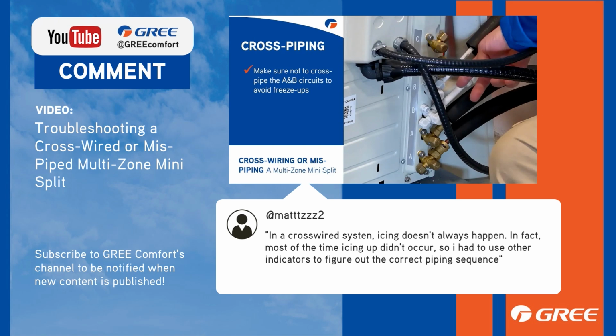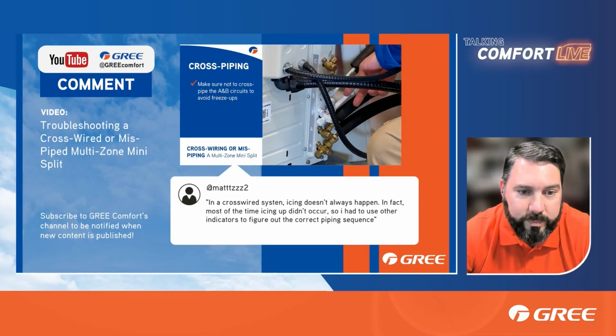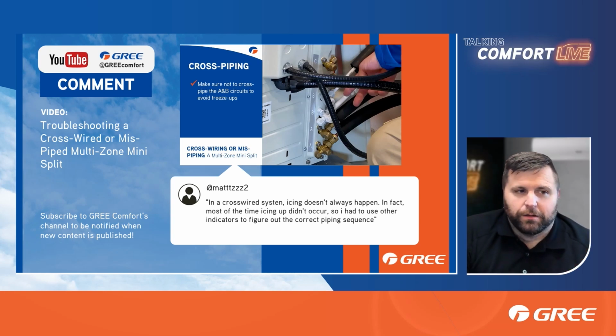In order for icing to occur, let's say this: if my unit is not calling for cooling, my blower still runs. Or if I had the blower set at medium or high, then the blower's on. It's going to be kind of hard for me to ice up at that point.